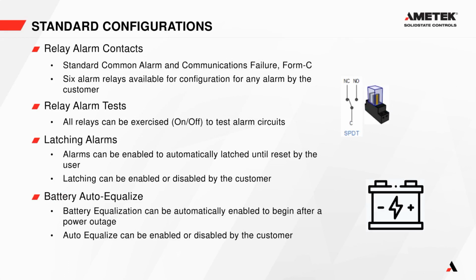In the standard configuration, we have 8 relay alarm contacts. The communications failure relay and common relay are always there, so we have 8 total relays, and 2 of them are always configured as those 2 alarms. The other 6 relays can be configured by the user using the LCD to indicate whatever alarm they would like. We also have a relay test function on the display that can turn all relays on or all relays off, so that the functionality can be tested to make sure the relays are not stuck open or welded shut.